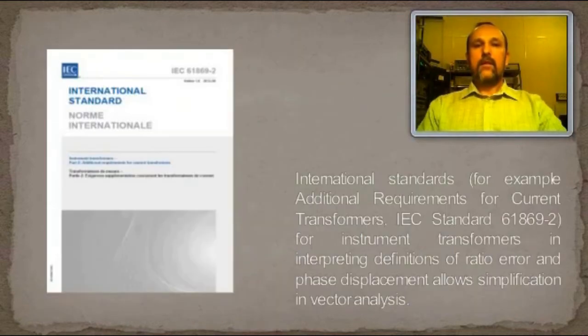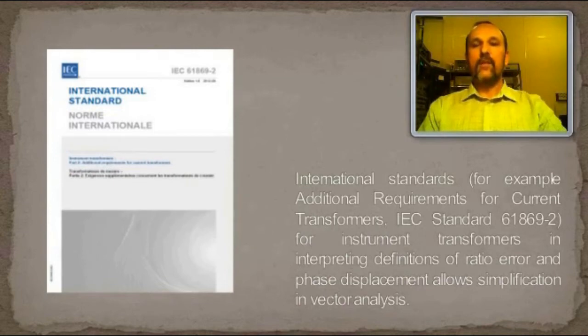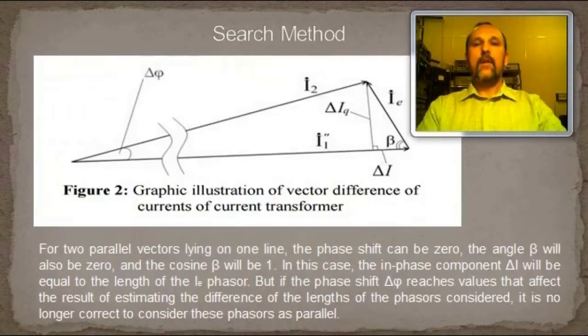International standards for instrument transformers in interpreting definitions of ratio error and phase displacement allows simplification in vector analysis. Finding the limits of the correctness of applying approximations when estimating errors of instrument transformers is a task which has not been widely highlighted. The purpose of this work is to establish the limitations for the correctness of the application of the simplified analysis of the interrelation between the phasors of secondary currents of the device under test and working standard, which is based on the assumption of parallelism of these two phasors.